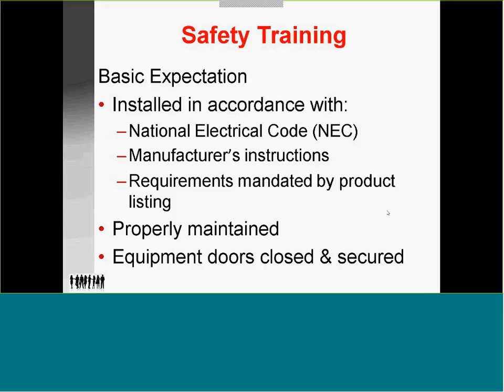And follow what is mandated by the product listing. The equipment itself must be properly maintained. NFPA 70E already brings in part of what is called 70B. It's the maintenance and care of electrical equipment. Disconnects, breakers, buckets in an MCC room, usually on the 480 side, are going to be required to be tested on a periodic basis. 70B is made up of many tables telling what has to be tested at what frequency, from annual all the way up to 15 years.